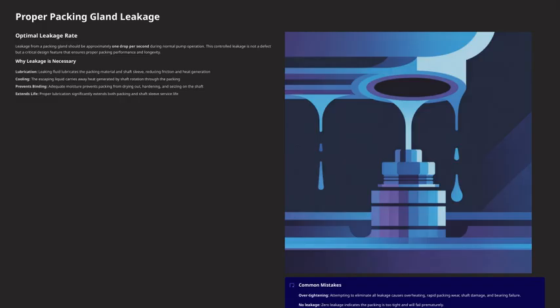First, it provides lubrication. The fluid that leaks out keeps the packing material and the shaft sleeve lubricated, reducing friction and heat buildup. Second, it helps cool the system. The escaping fluid carries away heat generated by the shaft's rotation. Third, it prevents the packing from drying out and hardening. Without enough moisture, the packing can seize on the shaft, causing damage. And finally, maintaining proper lubrication and cooling significantly extends the service life of both the packing and the shaft sleeve.